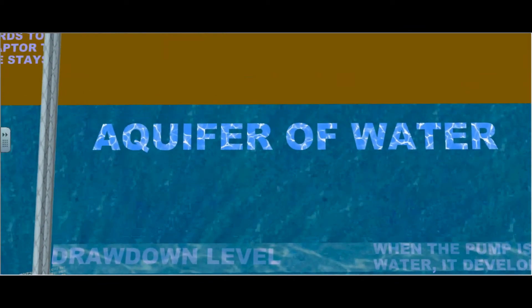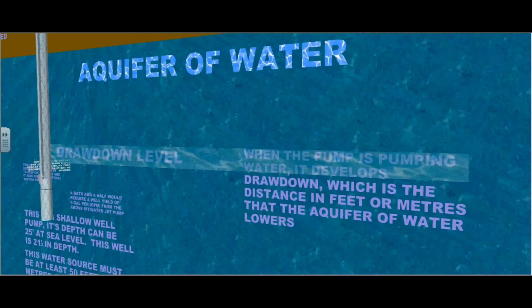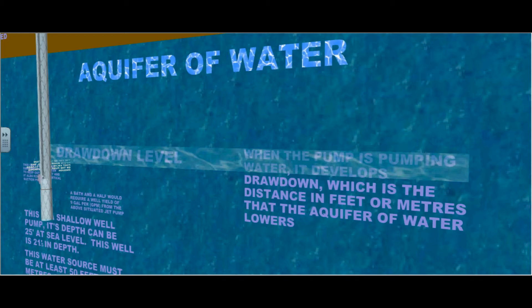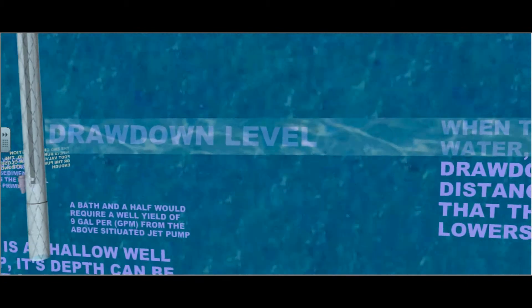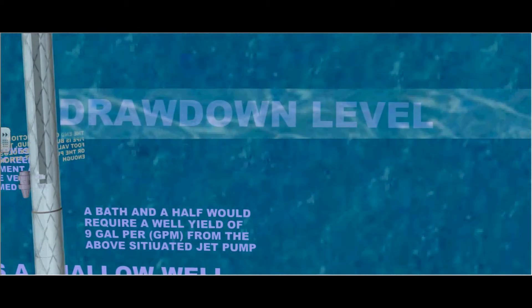This is an aquifer of water. When the pump is pumping water, it develops drawdown which is the distance in feet or meters that the aquifer of water lowers. It actually develops a cone which goes down to the drawdown level which must be above the foot valve.